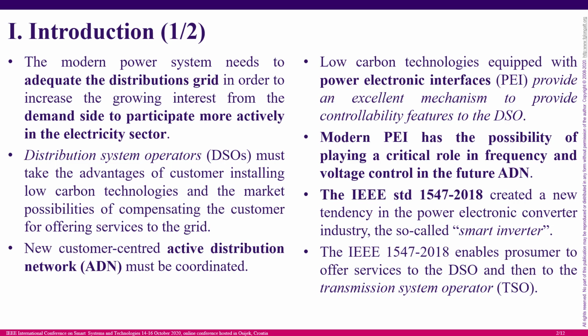The good news is that the power electronic interfaces used for low carbon technology are very versatile, and they offer an excellent mechanism to provide controllability features to the DSO. As a consequence, modern power electronic interfaces can play a crucial role in frequency and voltage control in the active distribution network. The IEEE standard 1547 from 2018 has created a new tendency inside the power sector, and that is the term smart inverter. A smart inverter is basically a power electronic converter that has several features in order to enhance the performance of the distribution system. And this IEEE 1547 enables the prosumer to offer services to the DSO, and as a consequence, the DSO can offer those services to the TSO.